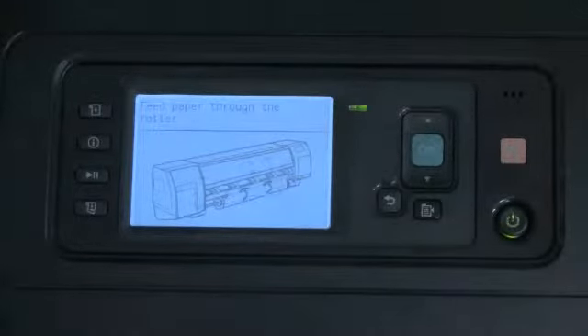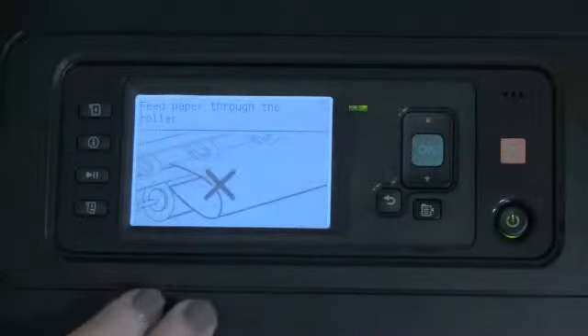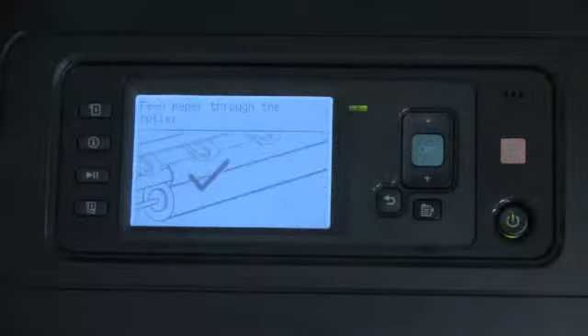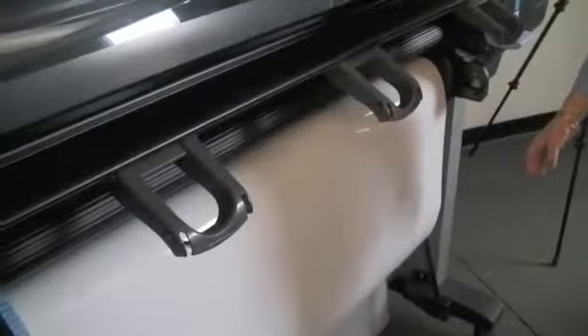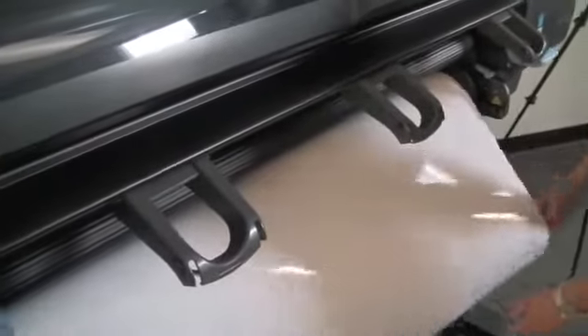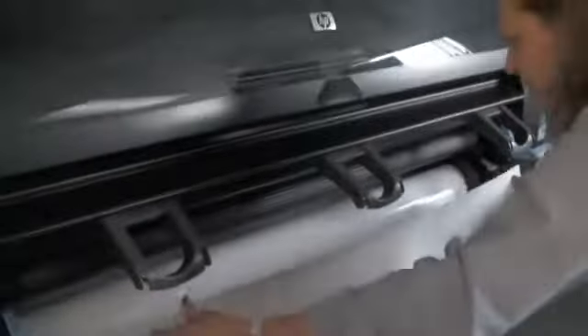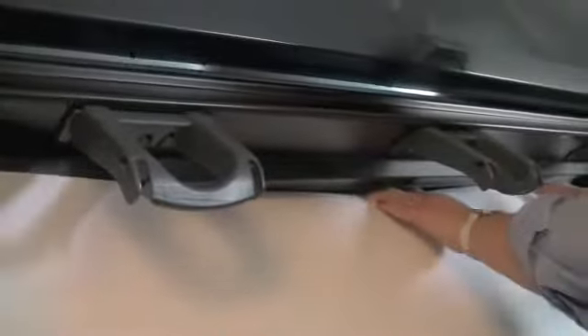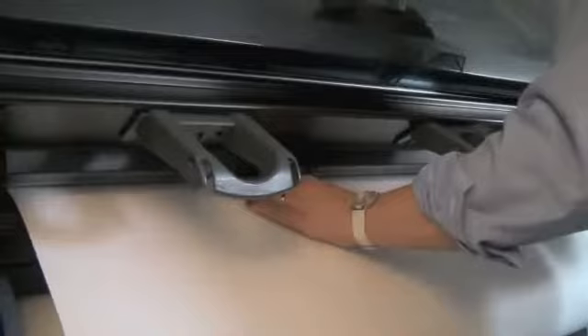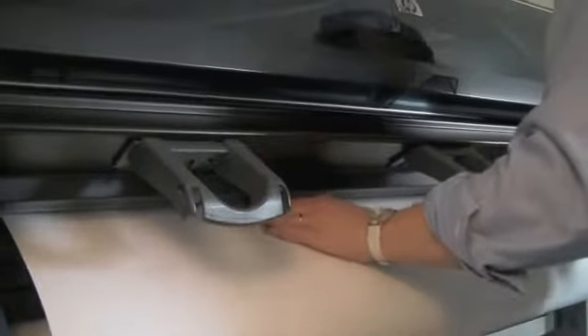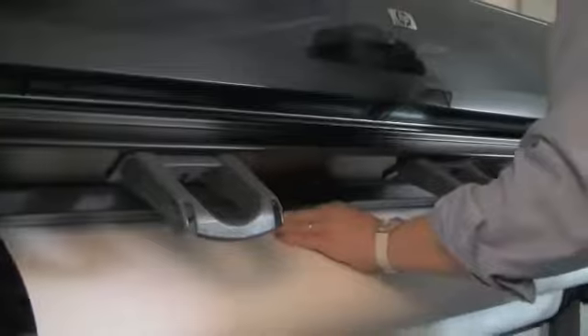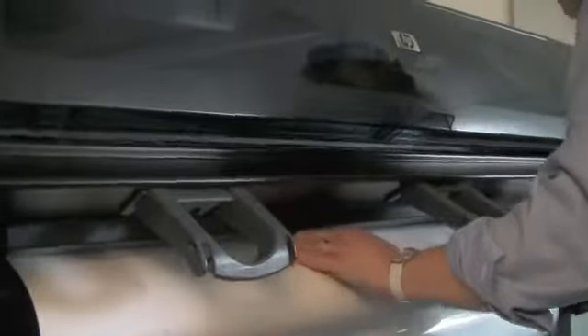And you can see, as I had mentioned in the previous module, it's showing an animation on the front panel that will show me exactly how to load media. So what we're ready to do now is to pull a couple of inches of media off of the spindle and move it into the paper path so that the printer will initiate its automatic media load sequence. What's going to happen is I'm going to do my level best to feed it in smoothly and evenly until I hear an audible beep. I should at this point begin to see the paper coming through the front portion of the printing platen.